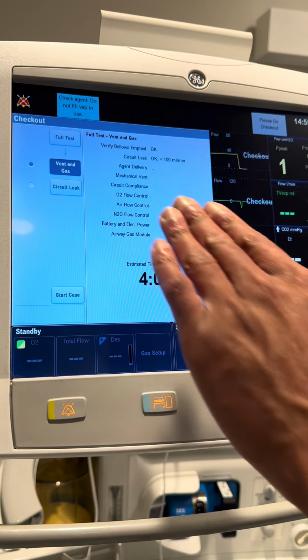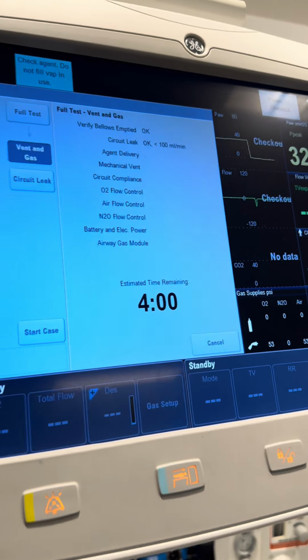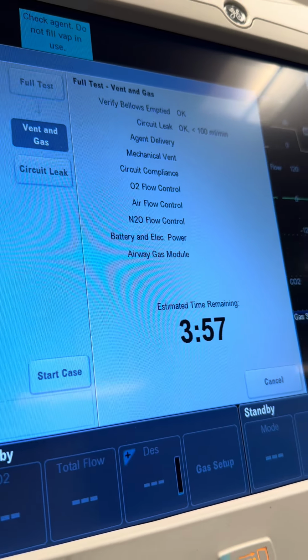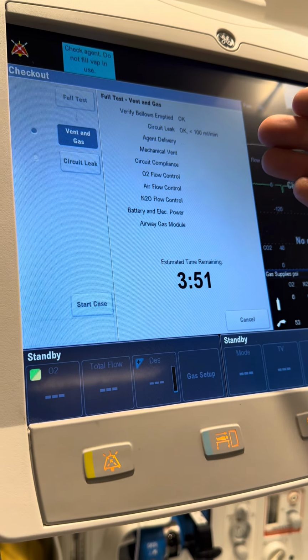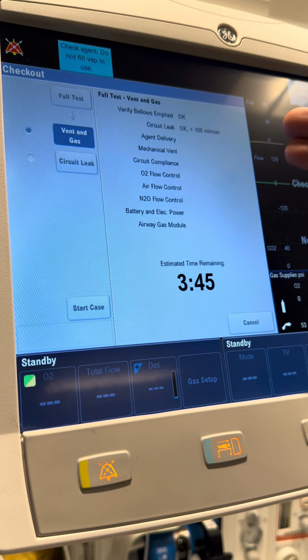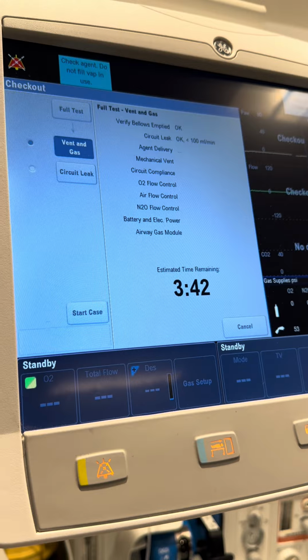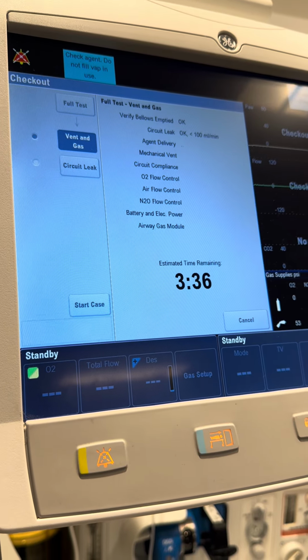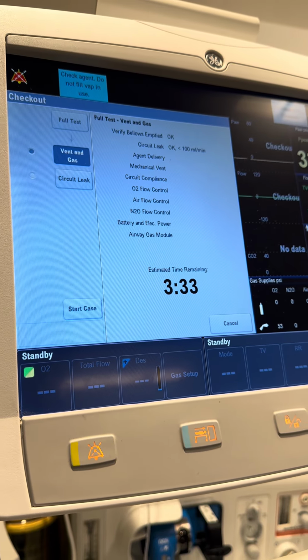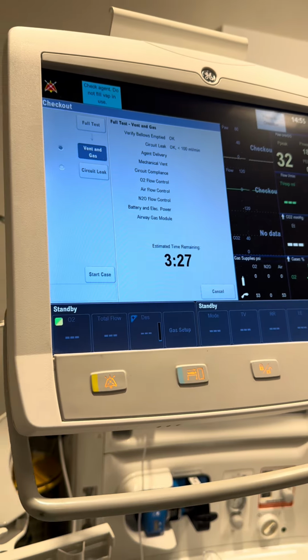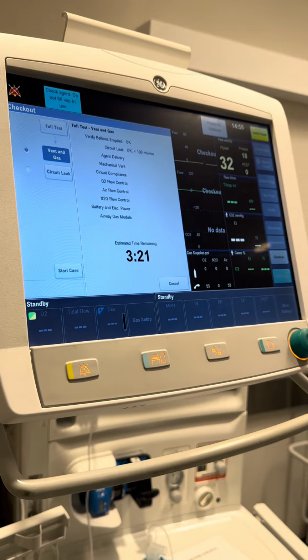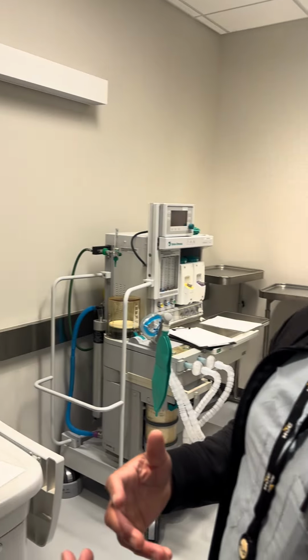So right here, it says circuit leak is less than 100 mils a minute, which is our target. Now, if there was some kind of yellow error on there where the leak was more than 100 mils a minute, we would have to reset, reassess, and try to figure out what exactly went wrong. Is it the bag? Is it the circuit? Is it the Sodasorb? We kind of have to check and make sure that everything was good and ready to go for the patient to be on the anesthesia machine.